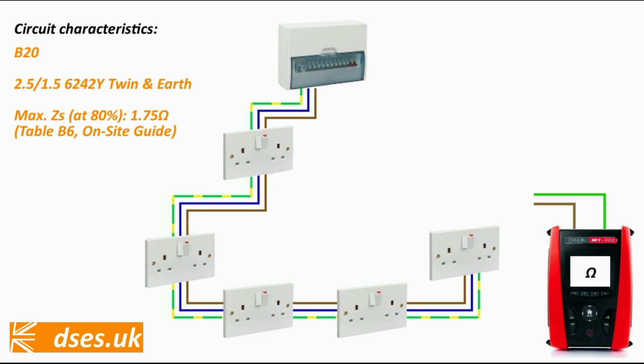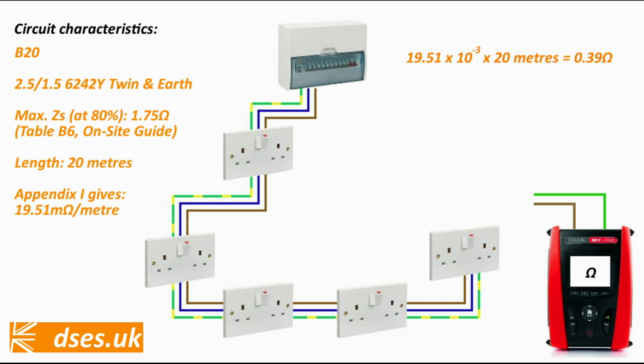and here's where it gets a bit sticky. Let's say our radial socket circuit here is 20 meters long. Appendix I of the On-Site Guide tells us that a 2.5mm² cable has a resistance of 19.51 milliohms per meter. So at 20 meters, we should see an R1 plus R2 reading of 0.39 ohms at the circuit endpoint. It may be very slightly higher to account for the fact the cable has been cut into at multiple points along the route to terminate into the other accessories, but if we see a reading of about 0.39 ohm and we believe that corresponds with the circuit length, then we can all start backslapping, as the result expected is the result obtained.